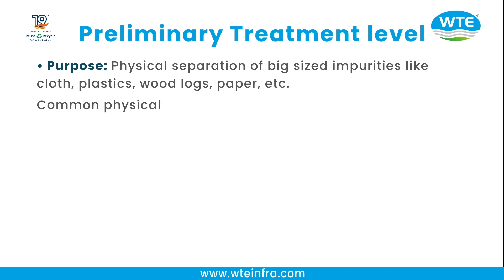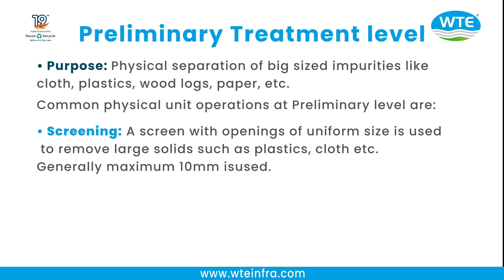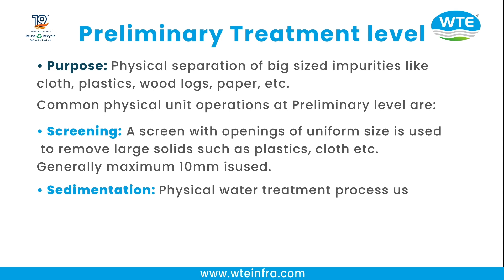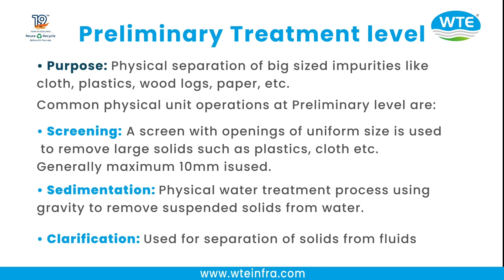Preliminary Treatment Level: Purpose is the physical separation of large-size impurities like cloth, plastic, wood, paper, etc. Common physical unit operations include Screening, where a screen with uniform-size openings (maximum 10 mm) removes large solids such as plastic and cloth. Sedimentation is a physical water treatment process using gravity to remove suspended solids from water. Clarification is used for separation of solids from fluids.